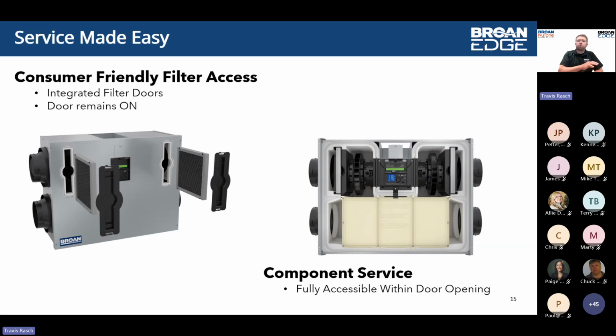So instead of the typical 1 year where we need to be vacuuming off that recovery core and removing that debris, with the Broan Edge models we will now go to a 3-year maintenance interval for that recovery core. Due to the materials the recovery core is made out of, we will actually be able to fully wash this recovery core. You could use a tub of water. I've seen people use bathtubs in the past with HRV cores to wash them. Even with this being an ERV recovery core type, with this new design you have the ability, every 3 years is what we're requiring, for that recovery core to physically be washed. Do yourself a favor, vacuum off all the big debris first, using a soft brush attachment on a vacuum. And then you are able to fully submerge this recovery core, like I said, in a tub of water or a bathtub, whatever you want to use.